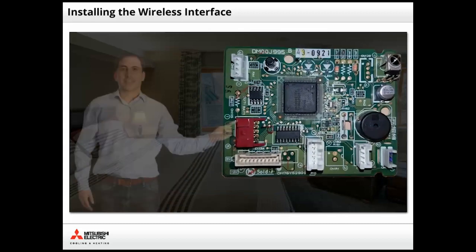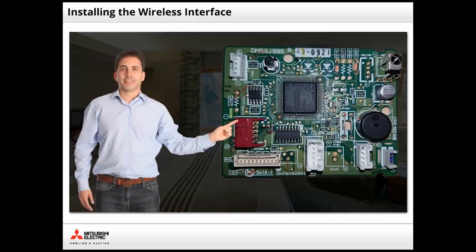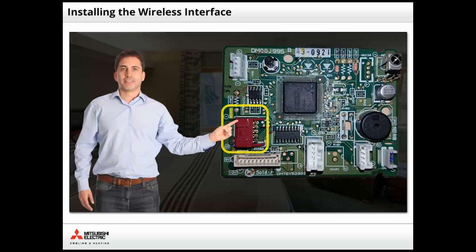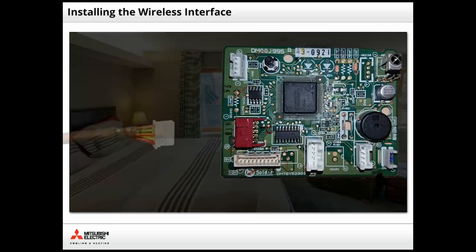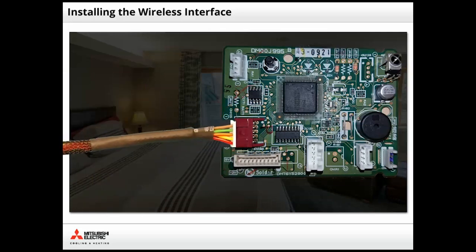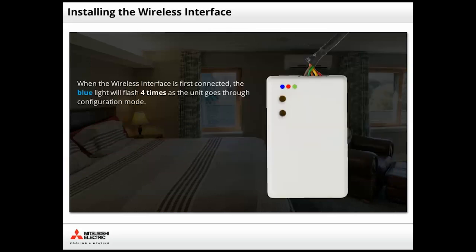Remove the unit's cover and locate CN105 on the indoor unit control board. This connector supplies both power and communication to the wireless interface. Holding the white connector of the wireless interface, slide it into the red connector on the board until you hear a click. Once connected, the lights on the wireless interface will illuminate.